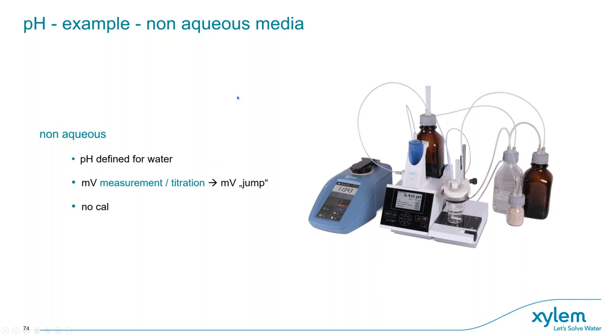pH is defined for water and not for any kind of solvent. However, you can measure relative values in solvents — for example in titration where you want to identify an endpoint rather than an exact pH value. In such cases, calibration does not make sense and is not needed or possible, because there is no water-based pH reference. You measure a relative, not an absolute, pH value.